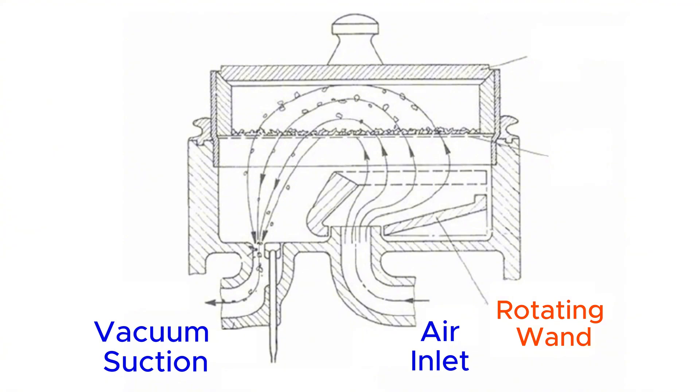Right above the air inlet, you have the rotating wand. The rotating wand works by forcing all the air coming through the inlet into a thin slit, creating an air blade. This air blade is positioned right below the sieve, and as it rotates, it clears up any particles clogging the sieve. It launches the particles at the lid, which breaks down any agglomeration, giving particles smaller than the mesh multiple opportunities to pass through.